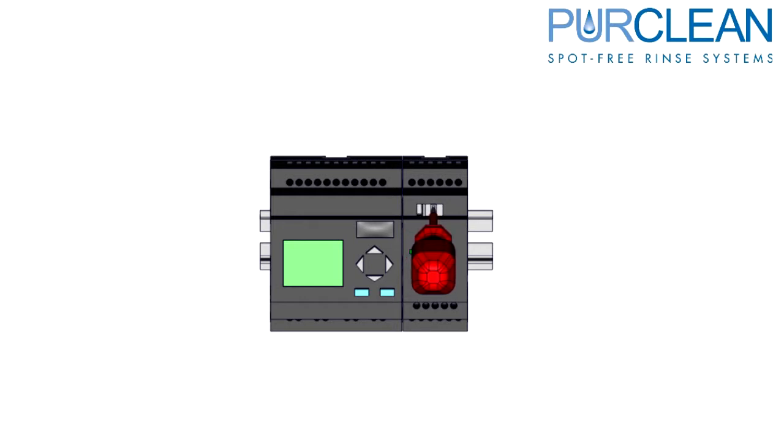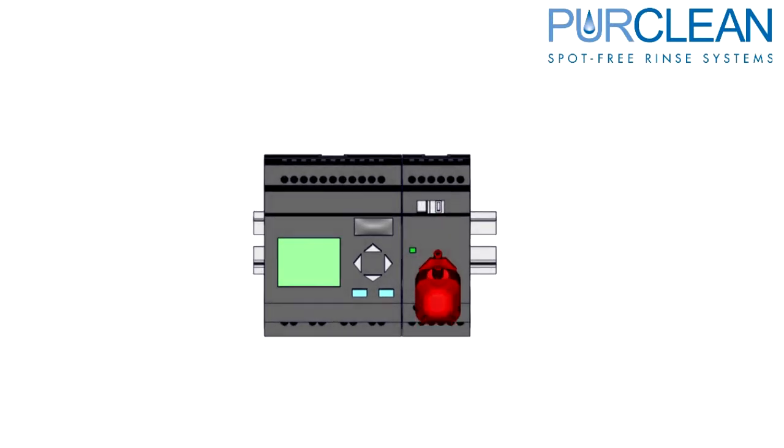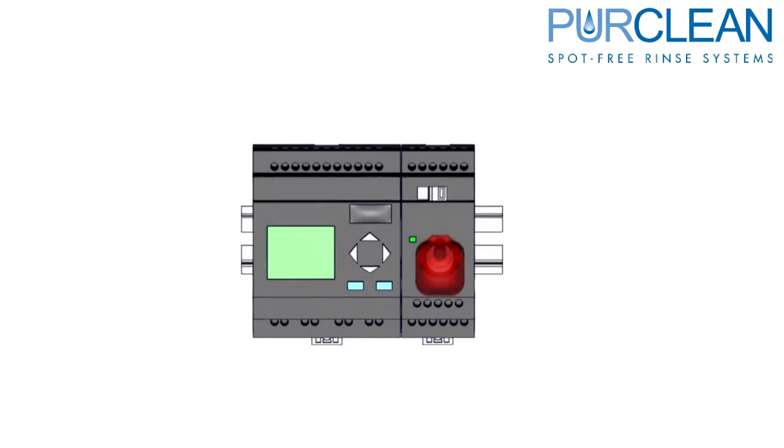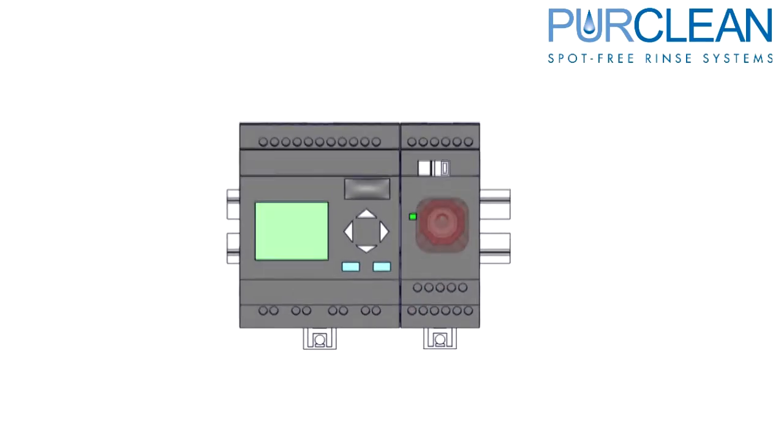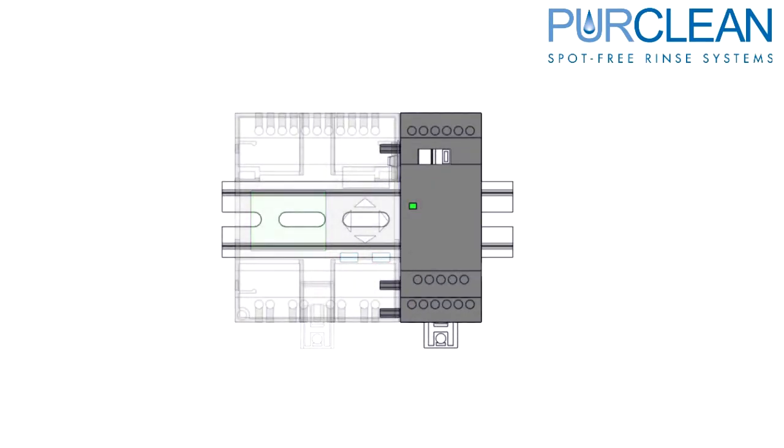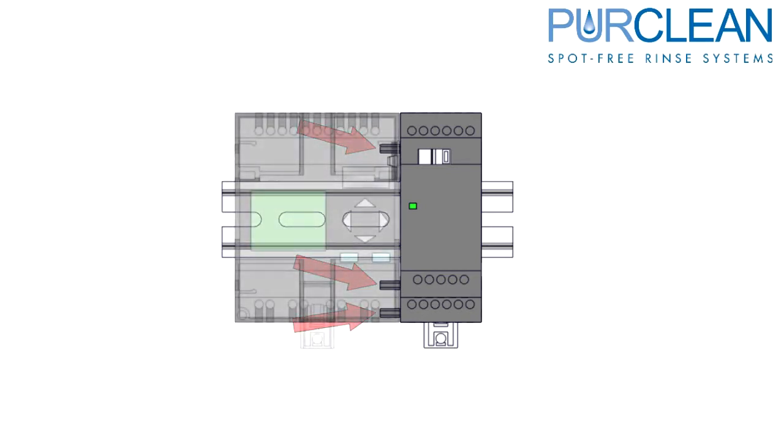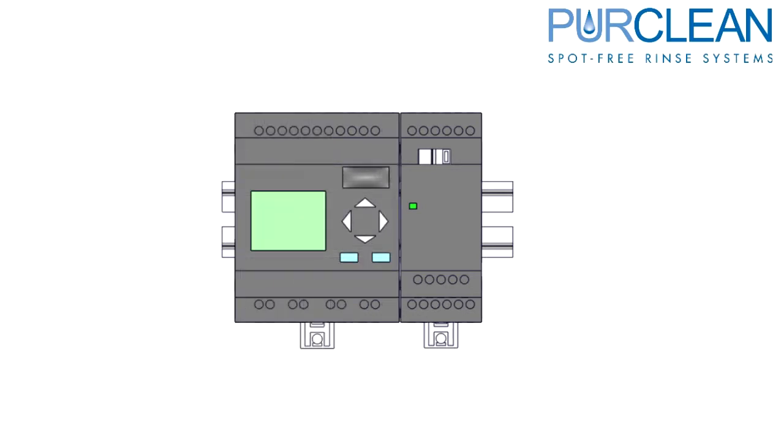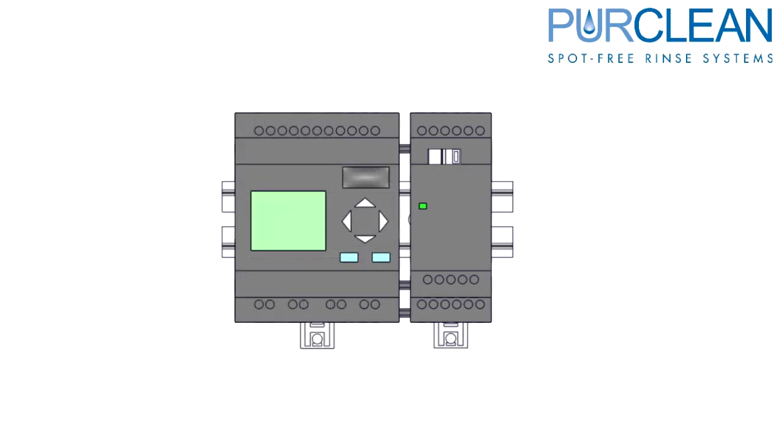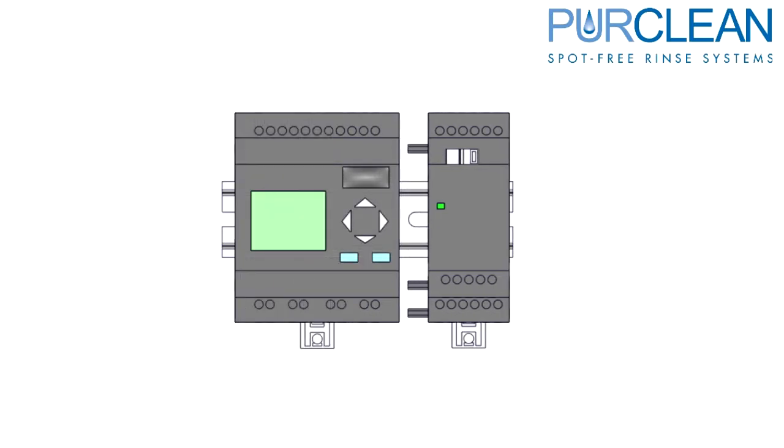Disconnect the communication tab on the extension by pushing down slightly and sliding it to the right. The PLC extension has three feet that slide into the main PLC. You will also need to separate the extension away from the main controller about a half an inch in order to remove the extension.